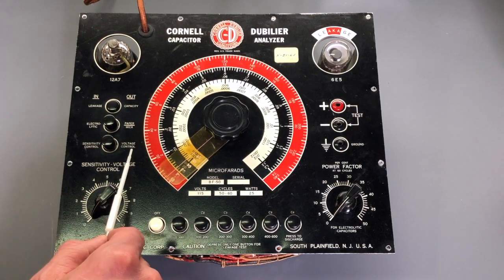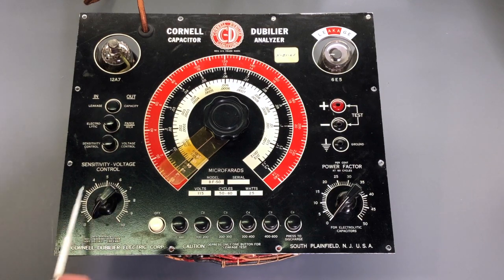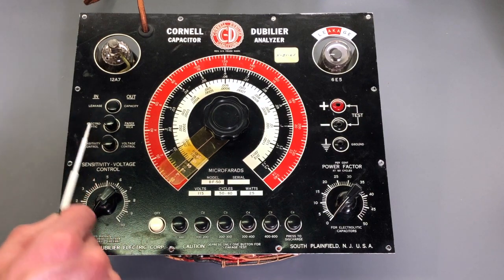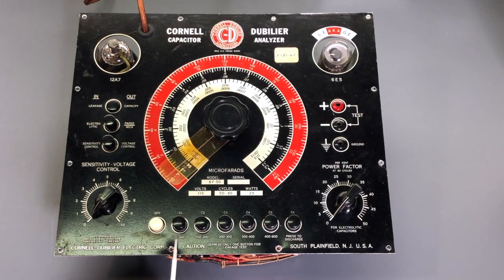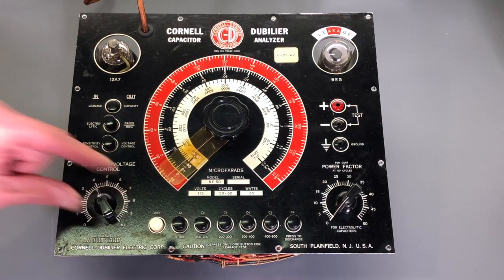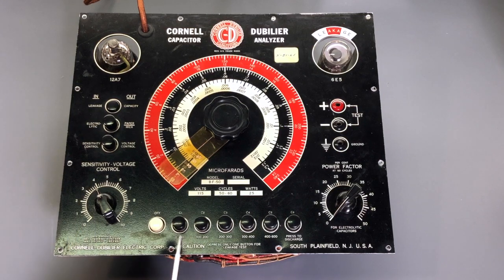The sensitivity and voltage control on this button are referring to this control right here. And on the leakage test, when you're using the electrolytic mode, these ranges are 0 to 100, 100 to 200, 200 to 300, 300 to 400, and then 400 to 600. The range is controlled by this voltage adjustment. So these are actually 10 volt steps, 10, 20, 30, and so on. So for example, if you were to select the 0 to 100 and position this at the 40 position here, you would actually have 40 volts on the output. If this was selected, it would be 140, 240, and so on.